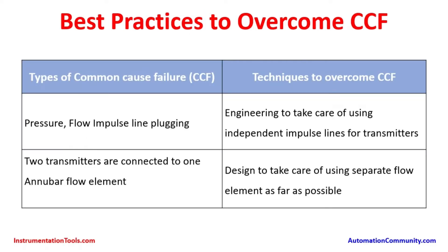Now we will go over the types of common cause failures and the techniques that can be adapted to overcome them. For pressure and flow transmitters with impulse line plugging, the engineering solution is to use independent impulse lines for each transmitter. Also consider diverse technology. If two transmitters are connected to one Annubar flow element, the design should use separate flow elements as far as the piping configuration and plant space allows.